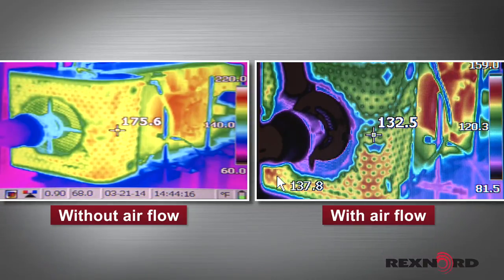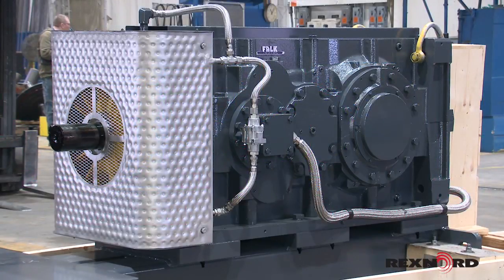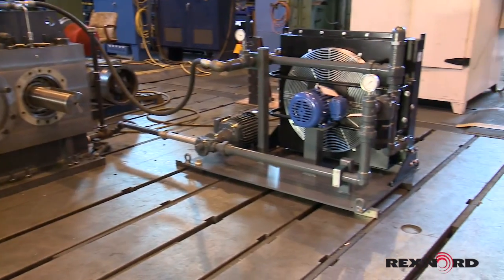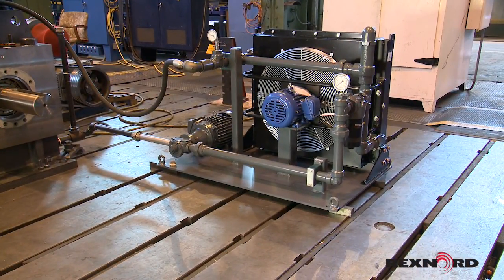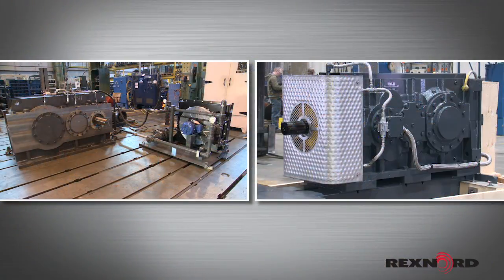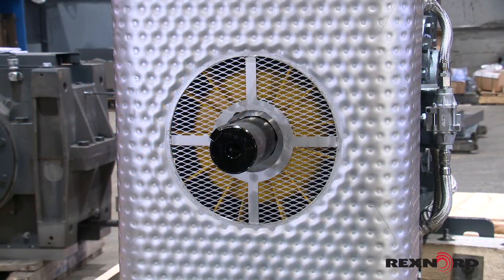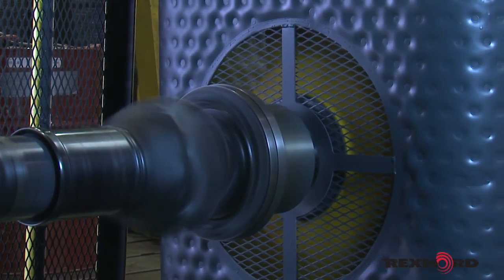Looking at the heat exchanger, we can also see that the oil is cooled less as it flows through the DuraPlate system. So we see that the DuraPlate cooling system is a simple and effective way to add additional thermal capacity to a V-Class gear reducer application. How does it compare to conventional forced air oil cooling? Note that the DuraPlate system is integral to the gear unit, barely extending the required space envelope. A separate cooler must either attach to the gear unit or have its own mounting base, adding cost to both transport and installation. It also increases the likelihood of damaging the cooling unit during handling. Also note that the DuraPlate heat exchanger is heavy gauge stainless steel, and the hoses are protected by braided stainless steel. The DuraPlate system will resist damage from inevitable bumps in an aggressive industrial environment.